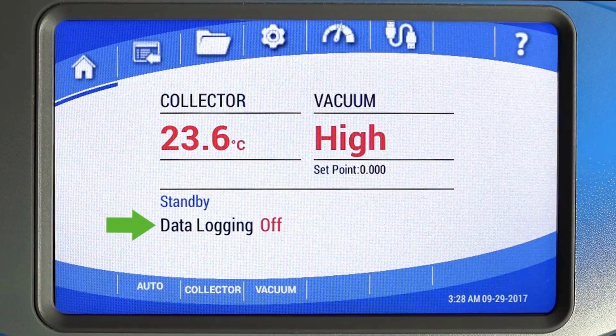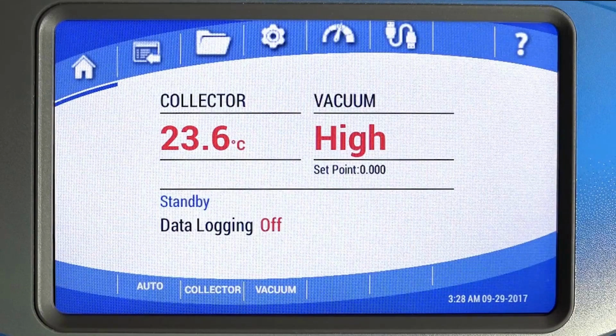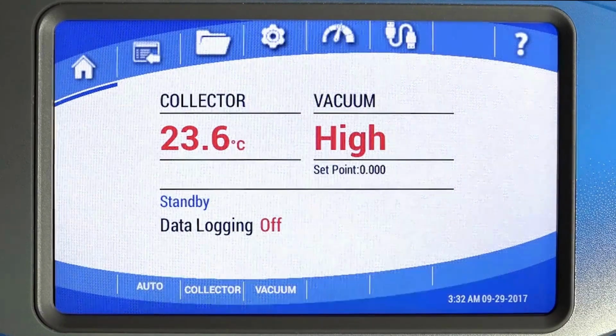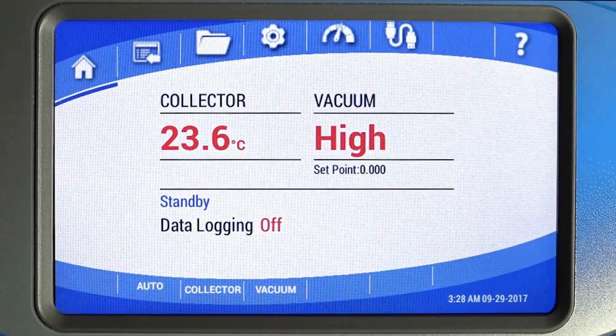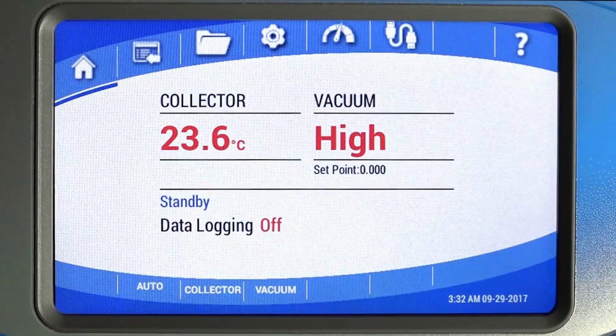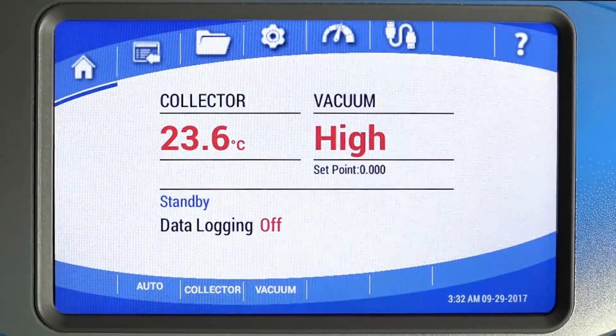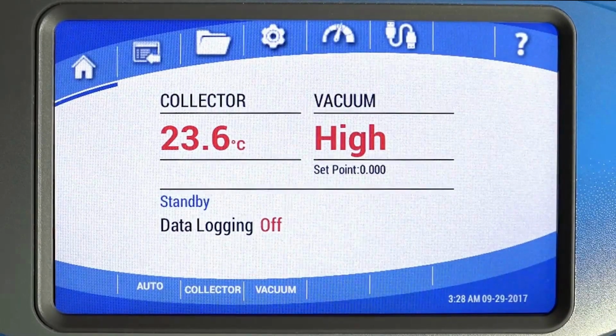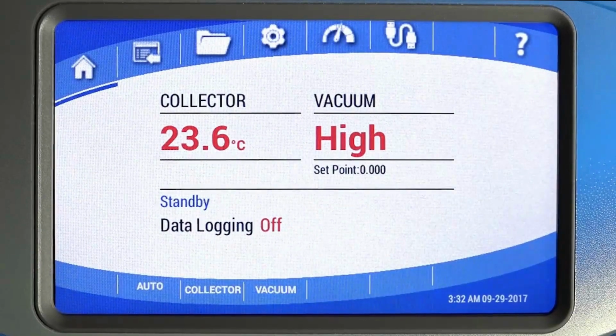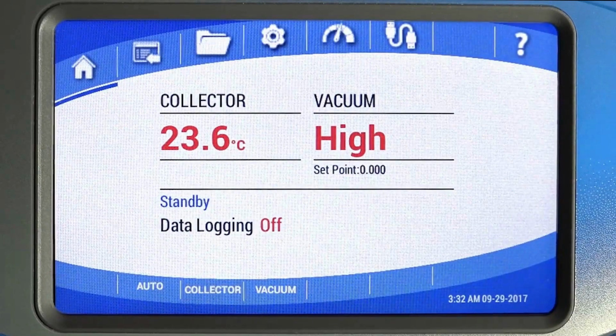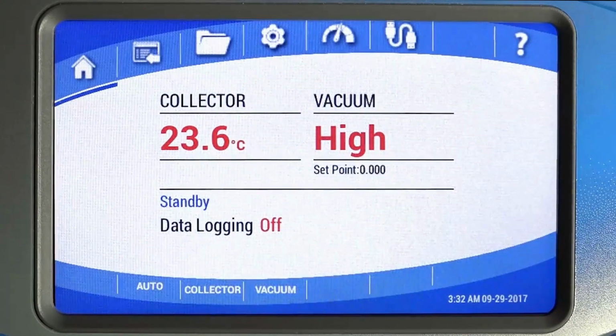Data logging status, on or off, will be displayed here. The buttons along the bottom control the collector, pump, and optional purge valve and shelf freezer, or mini chamber. The auto button allows you to initiate the automatic startup sequence. Upon pushing, the collector starts, and the vacuum is automatically started after the collector temperature reaches -40 degrees Celsius. Or use the collector/defrost and vacuum buttons to manually turn the collector and vacuum pump on and off.